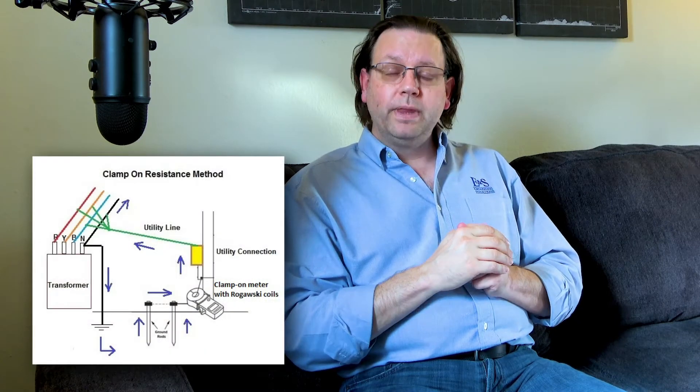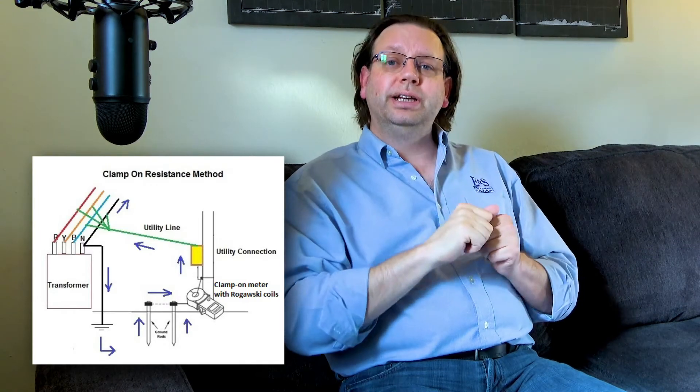Traditionally, the way to think about this test: on the side of your home, you have a single ground rod installed — a 10-foot rod driven into the earth, one connection, one rod. You clamp onto that wire and inject a signal. The Rogowski coil oscillates back and forth, inducing a current down into that copper wire. That current goes both directions — part goes up into your electrical box, through the neutral-to-ground bond, up the neutral wire, to the utility pole's transformer. It hits that transformer, which is tied to the X0 and the chassis, which has a grounding electrode. It goes down the utility company's ground rod, across the earth, back up your ground rod, and to your meter.